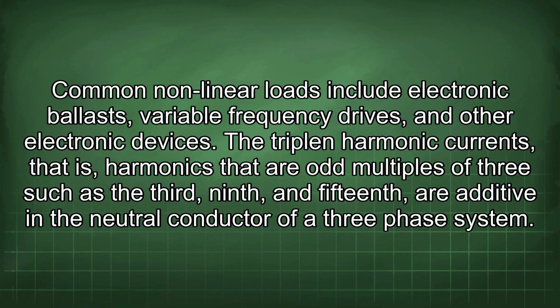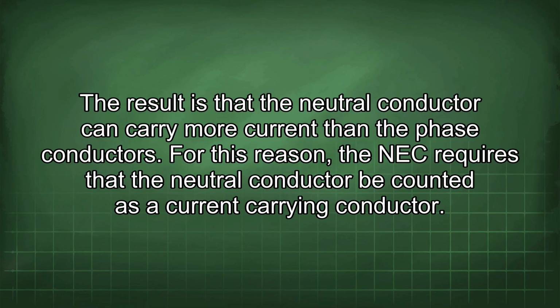The triplen harmonic currents, that is, harmonics that are odd multiples of 3 such as the 3rd, 9th, and 15th, are additive in the neutral conductor of a 3-phase system. The result is that the neutral conductor can carry more current than the phase conductors. For this reason, the NEC requires that the neutral conductor be counted as a current-carrying conductor.